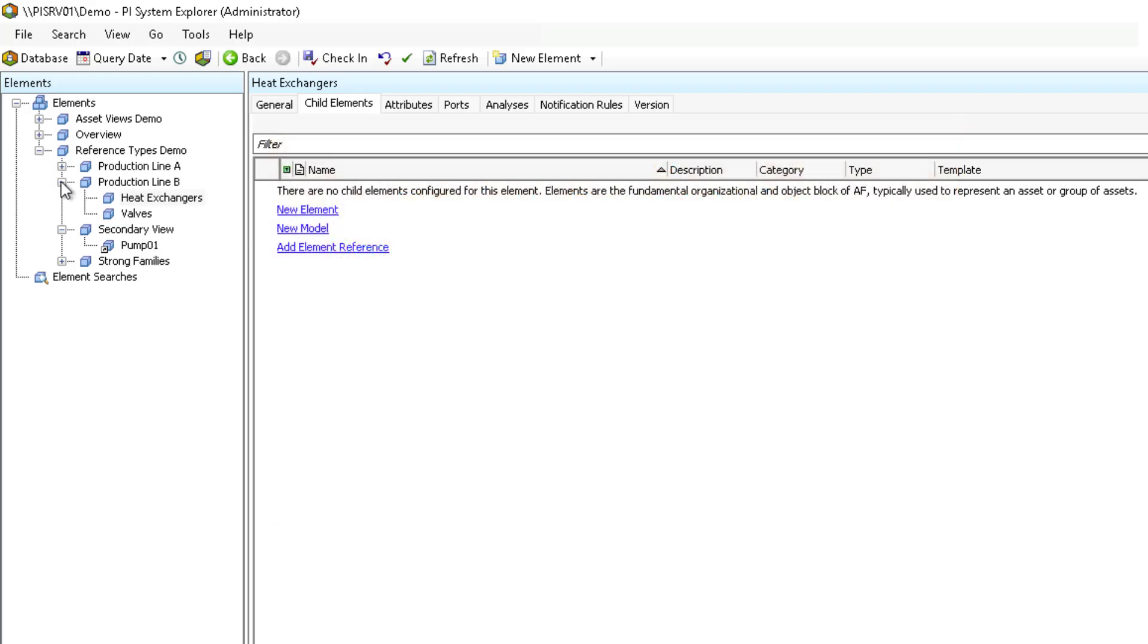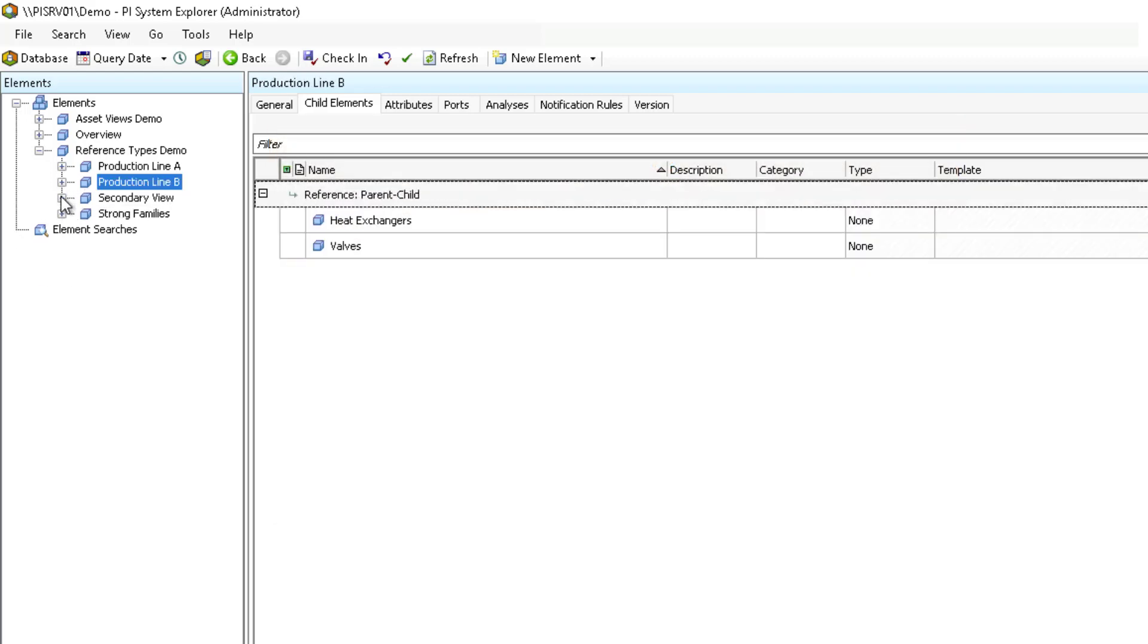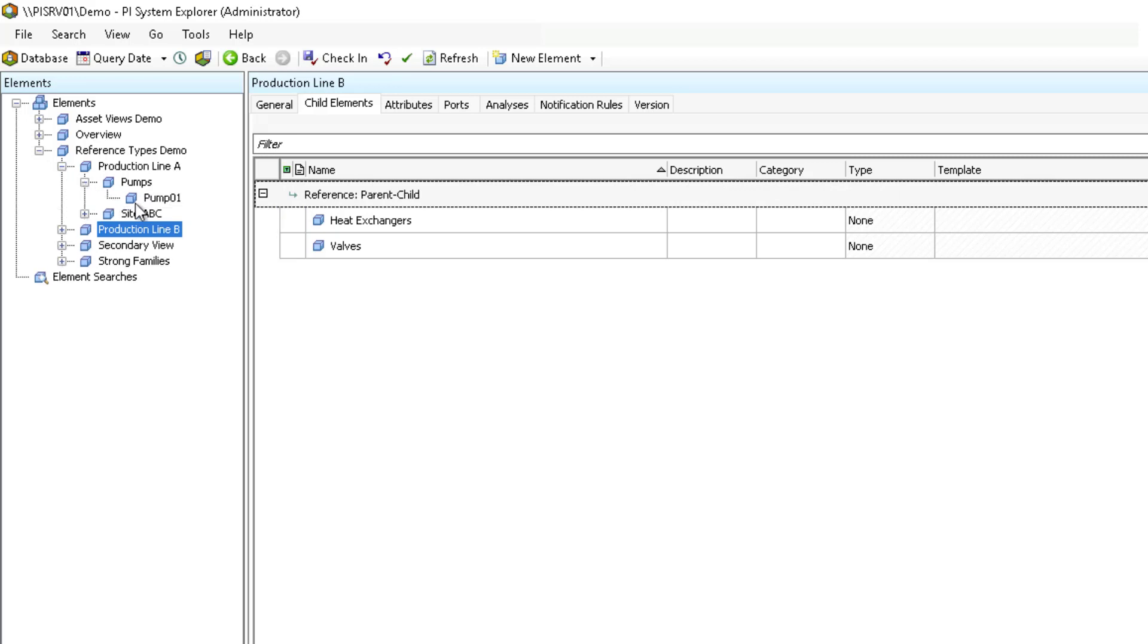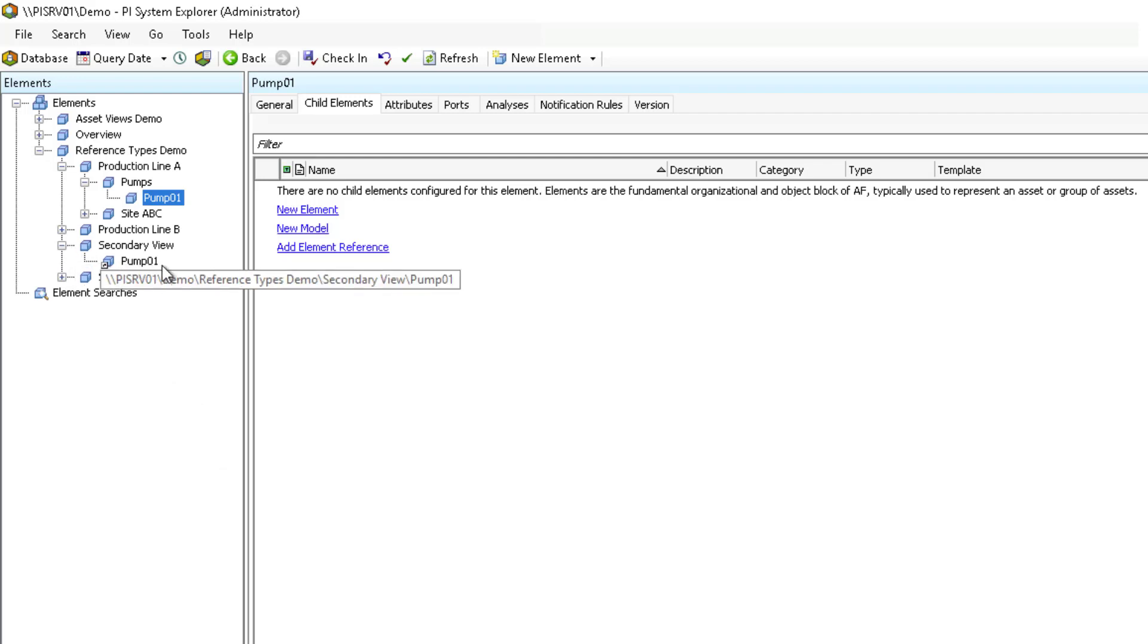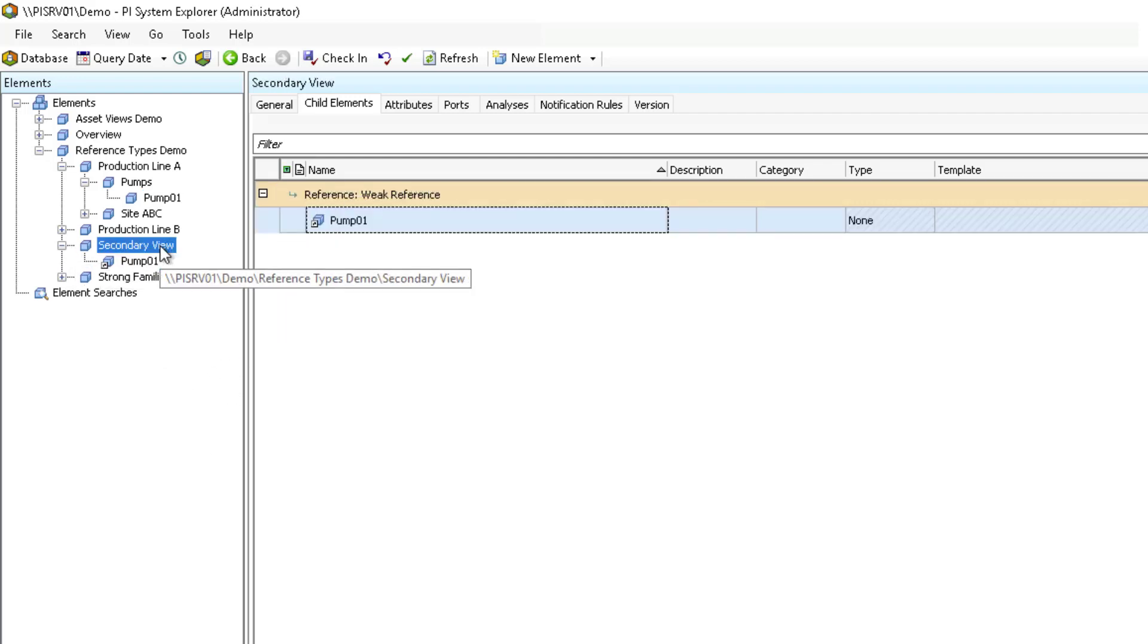Now let's show an example of a weak reference enabling two different views of our hierarchy in PI AF. Pump 01 is located as a child under Production Line A Pumps. This is the main view for Pump 01 and has a parent-child reference. An element reference for Pump 01 also exists below the secondary view element. For this view, the reference type between secondary view and Pump 01 element reference is a weak reference.